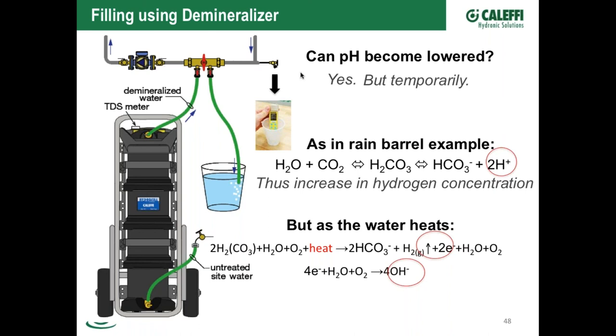But what happens in a closed hydronic system is different than what happens in an open system with low pH. Here's an example: let's say you have low pH to begin with, like from your demineralizer or reclaimed rainwater put into your system—however it started off low, it's temporary. What happens in a hydronic system, as in the rain barrel example, is that water, H2O, reacts with carbon dioxide to create H2CO3, carbonic acid. The carbonic acid dissociates into bicarbonate and hydrogen, and those positive charges on the hydrogen—remember pH is defined by the increase in hydrogen ionic activity versus hydroxide—cause your pH to drop. That's what's happening with rain as an example.